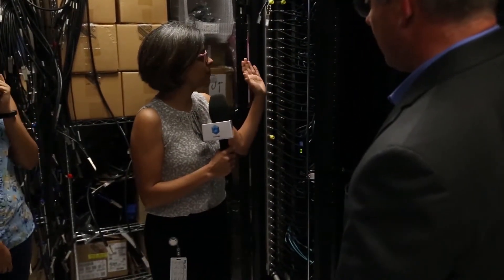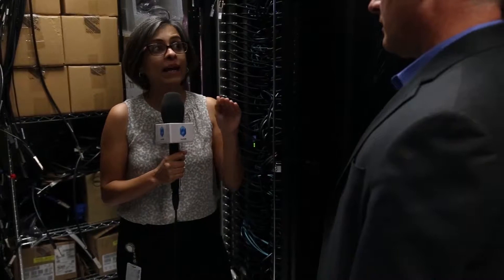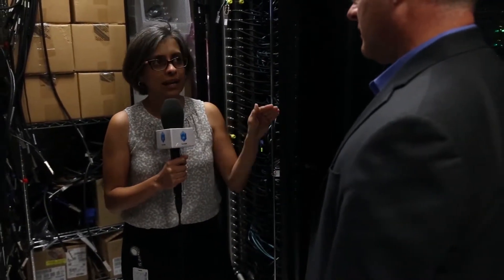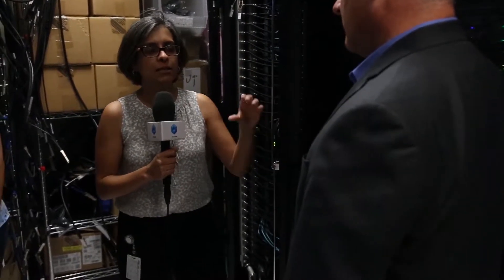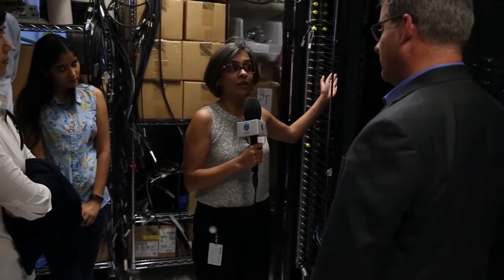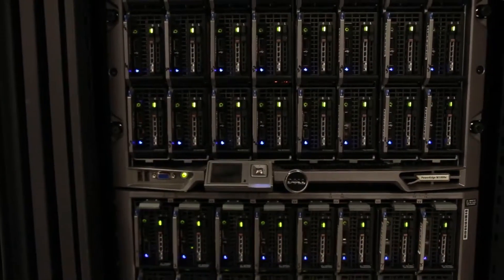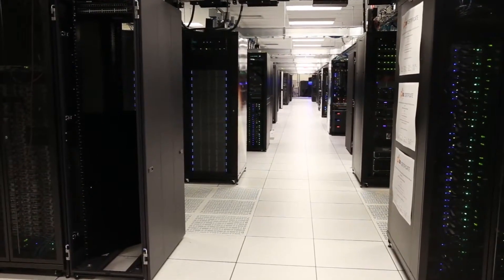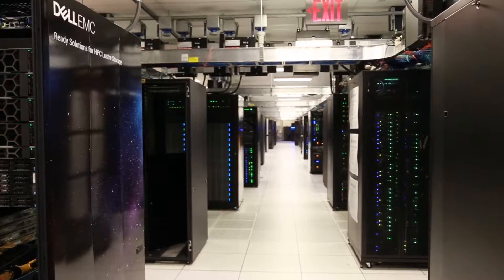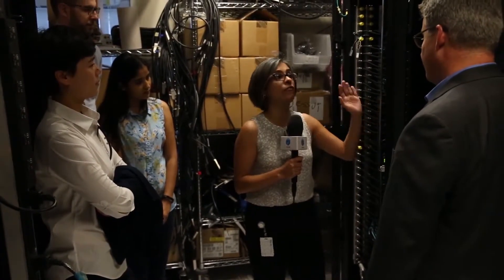In our early studies, we have seen that your efficiency in terms of how much performance you get out of the server should not matter whether you're air-cooled or liquid-cooled, if your air-cooling solution can provide enough cooling for your components. So if you have a well air-cooled solution, it's not going to perform any worse than a liquid-cooled solution. What liquid-cooling allows you to do is put a higher level configuration in the same rack space — higher TDP processors, more disks — a configuration that you cannot adequately air-cool, you will be able to liquid-cool in the same space with the same airflow.